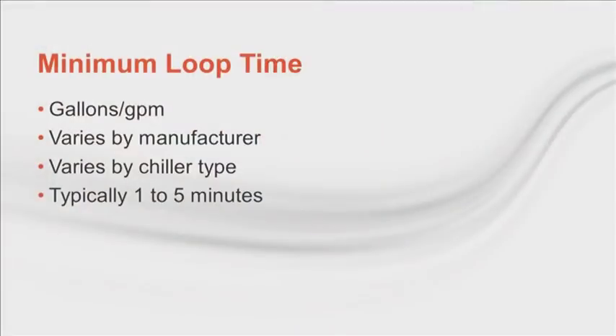There's another advantage of a lower design flow rate in the design phase. It increases loop time if you don't downsize the pipes. Now, chillers have a minimum loop time. One way to calculate the loop time of your system is by dividing gallons by GPM. It's the amount of time it takes for the chiller to see the same water after it's been circulated. If you don't have a long enough loop time, the chiller controls would likely become unstable and the system would perform poorly or unreliably. The required loop time varies by manufacturer and by chiller type.